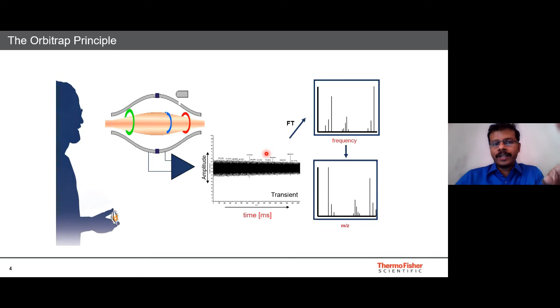So in principle, ion populations are moving around the central electrode, and they are moving with certain frequency. This frequency of movement generates image current. The image current is later being transformed using the algorithm FT, Fourier transform. Ultimately, the output that we see is the spectral plot, m/z spectral plot. So this is how the Orbitrap mass analyzer detects our samples or the analyte ions of interest and generates the m/z spectral plot. Now let's go into the next slide.